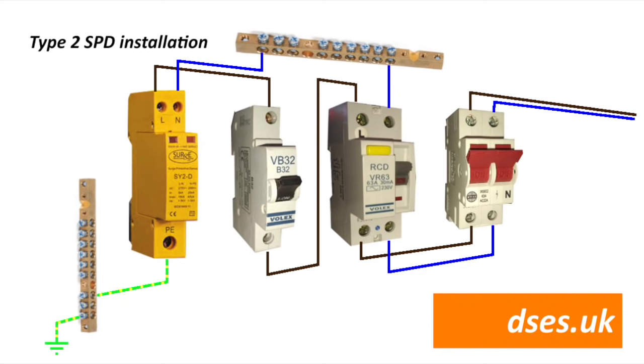If there's no space in the existing CU to accommodate it, then it can be installed in another enclosure adjacent to the CU. Regulation 534.4.10 requires a Type 2 SPD to have an earthing conductor with a CSA of 6mm², and for its supply conductors to be appropriately rated for the breaker in use, but to be of a size of no less than 2.5mm. So you can use 2.5mm for a 16 or 20 amp MCB, maybe bob up to 4 or 6mm if hanging off a 32 amp, although I don't know if I'd bother. For a Type 1 SPD, minimum CSA is 16mm for the earth and 6mm for the supply conductors.